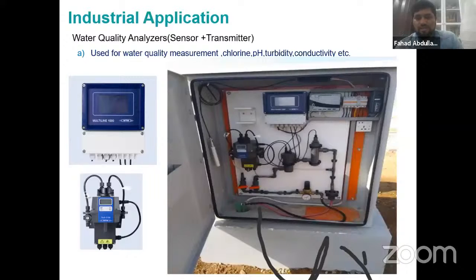Yes, actually it is not installed directly on the pipe. A sample is taken from the pipe. In this picture you can see some green pipes coming - from the main line, a sampling line is taken, and then this water goes through the sensor and it measures it, and the outlet is drained. This water will not go back to the pipeline again - only fresh water comes to the sensor.